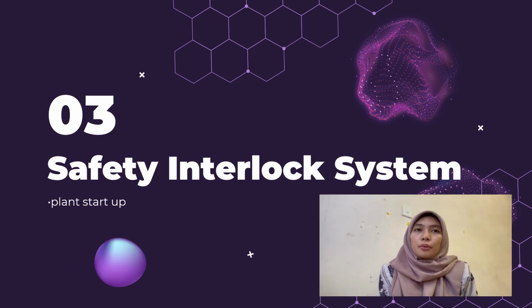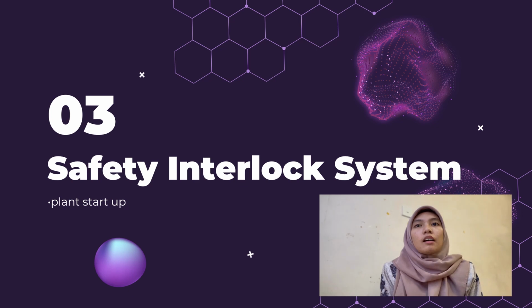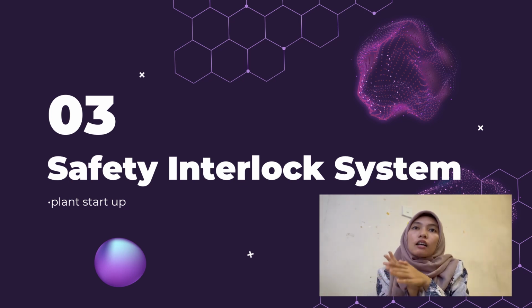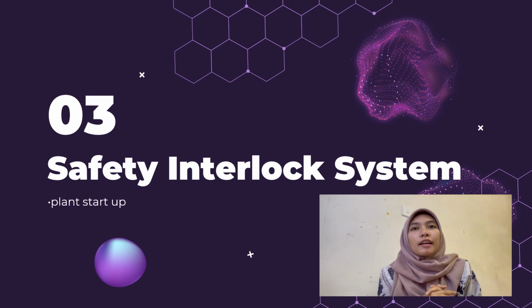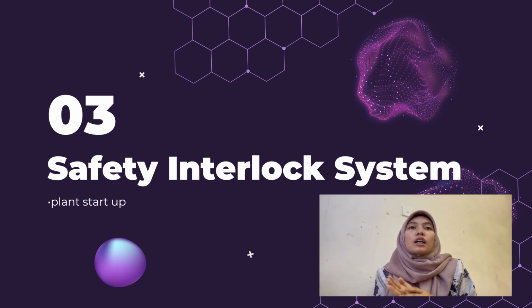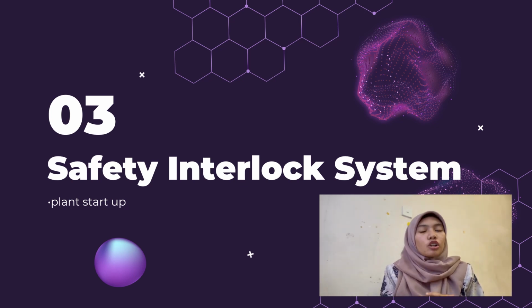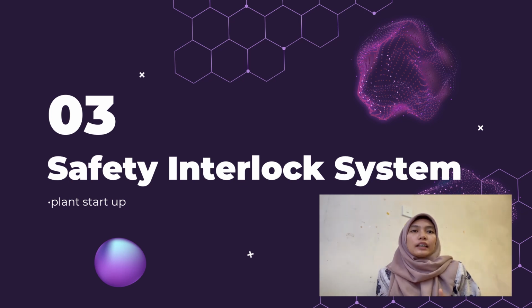Next, I'm going to give an example for the safety interlock system. This one is for the plant startup. During plant startup, interlocks can provide safety protection by requiring that certain permissible conditions exist before proceeding to the next stage. For example, an incinerator must be inert purged and free of hydrocarbon gases before light up.